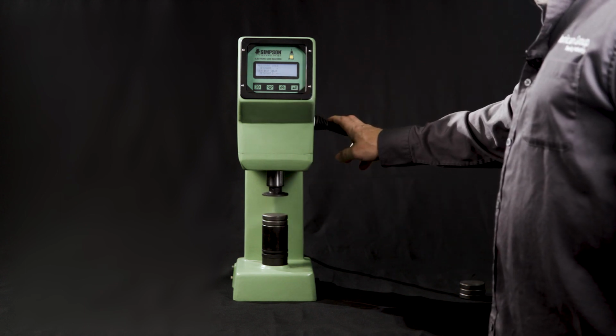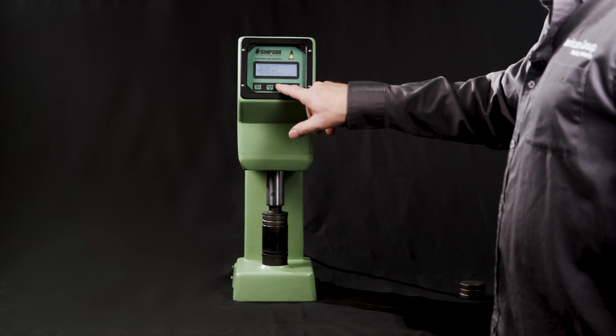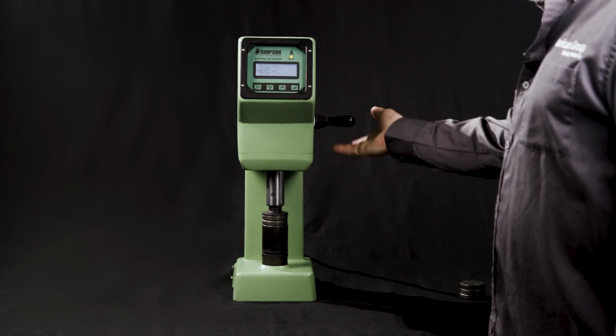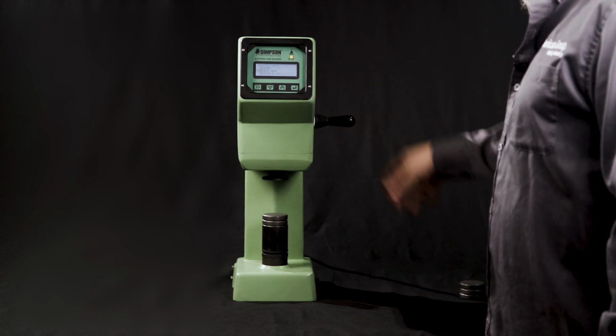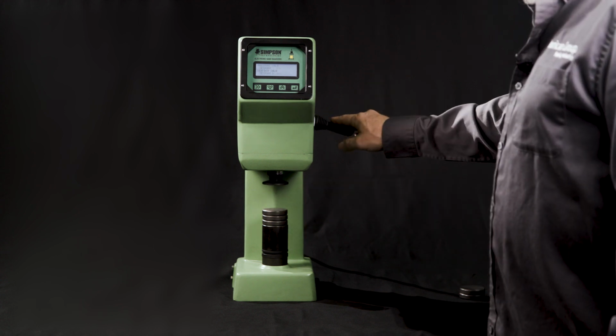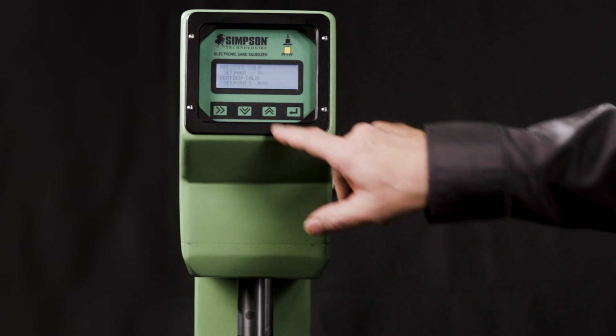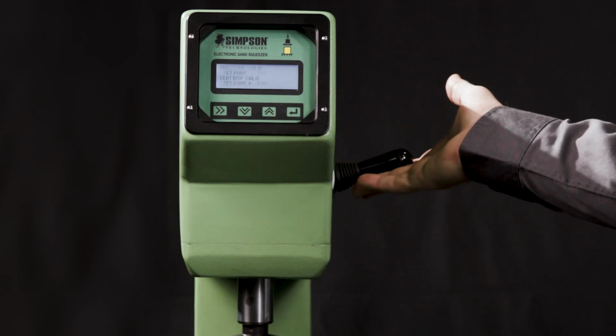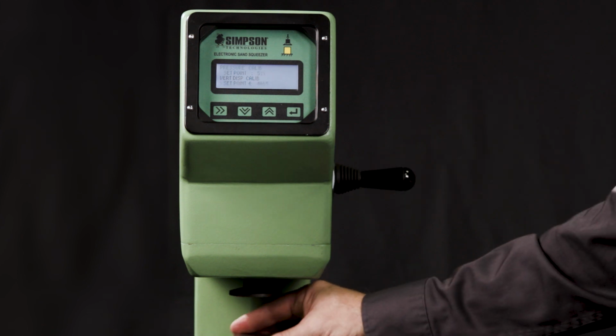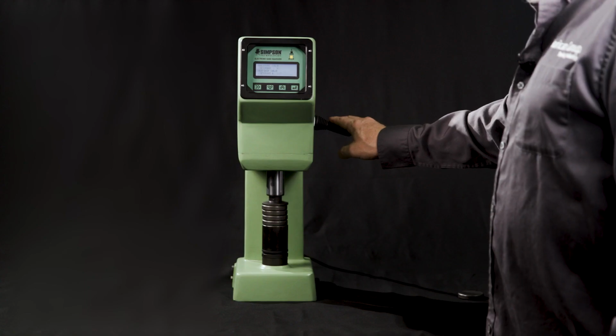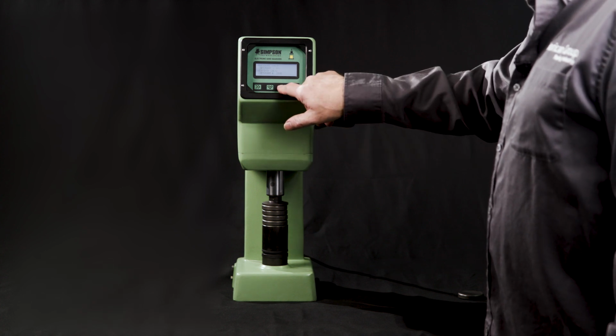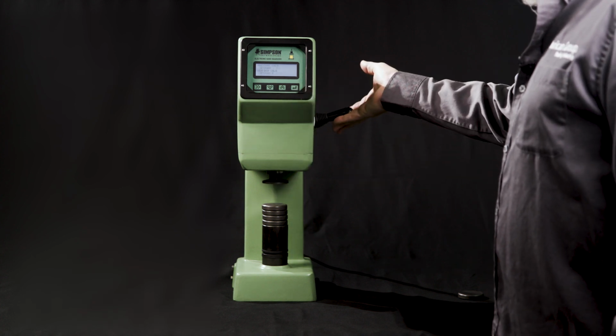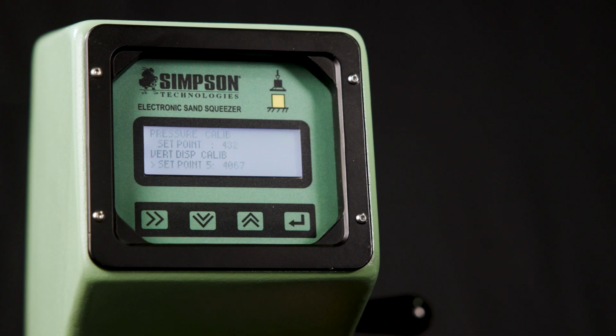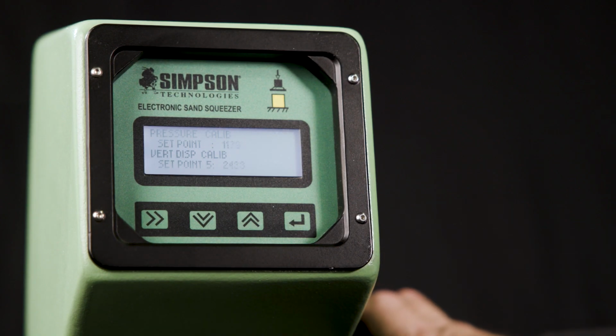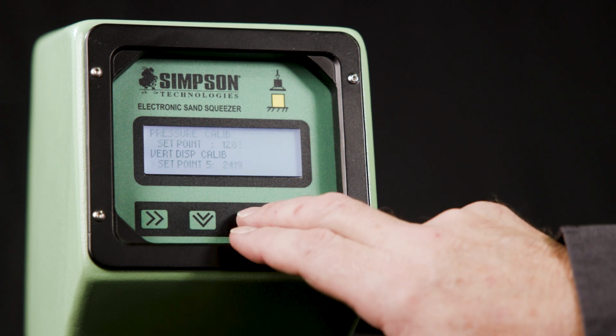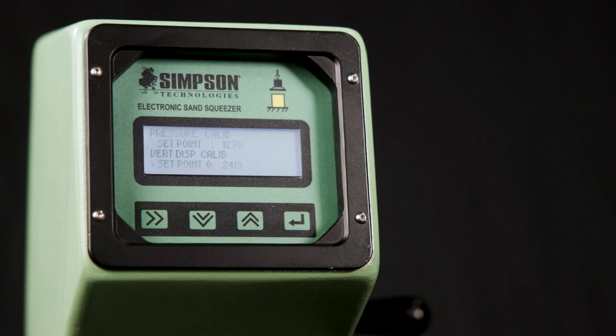Put the next one in, bring this down, stabilize. Up arrow goes to set point 3. Bring this down. Up arrow, bring this back up. Next point. Bring this down. Set point 5. Put the last one in. Press this button here. If you've done it all correctly, it will go back to 0, and that is it for the linear calibration.